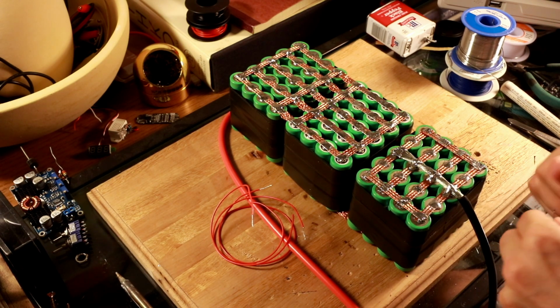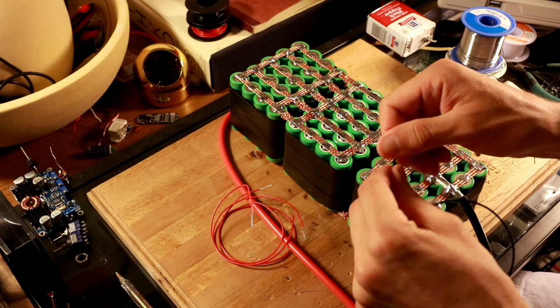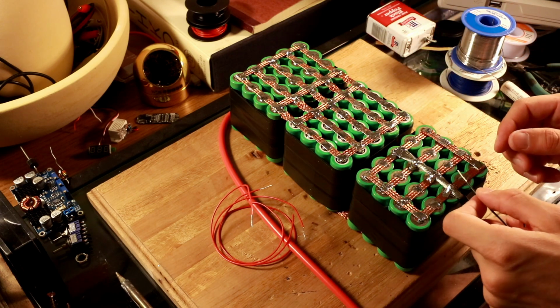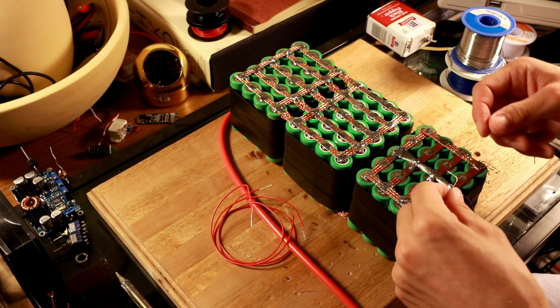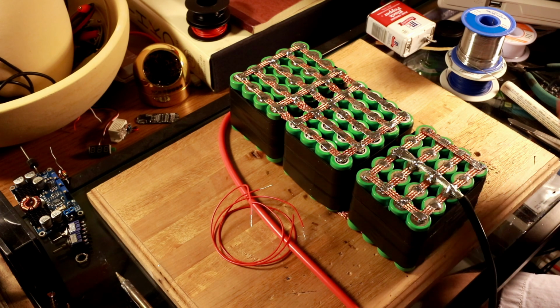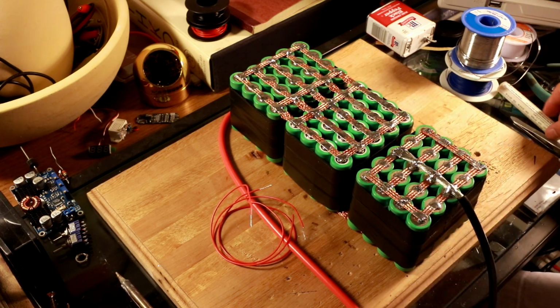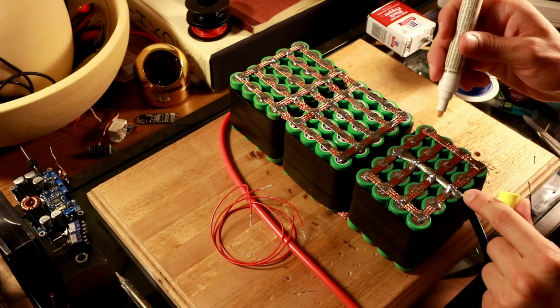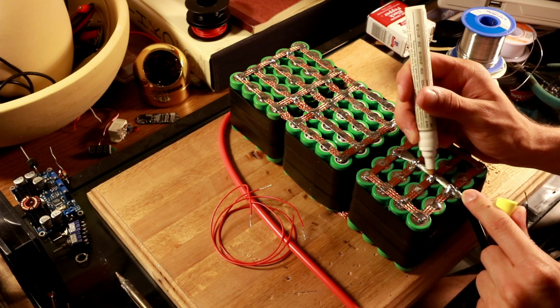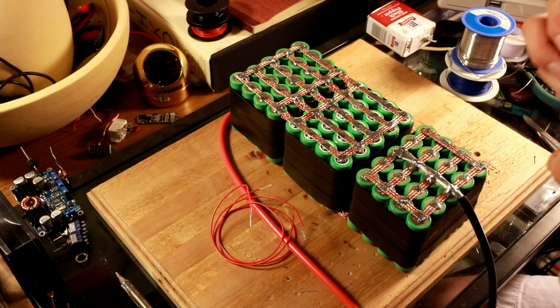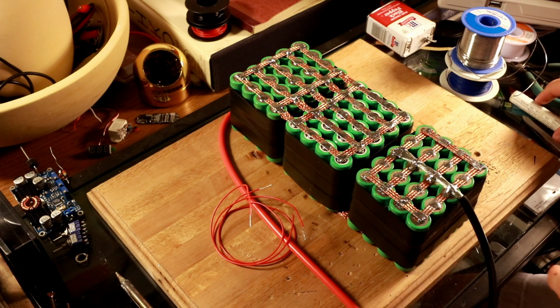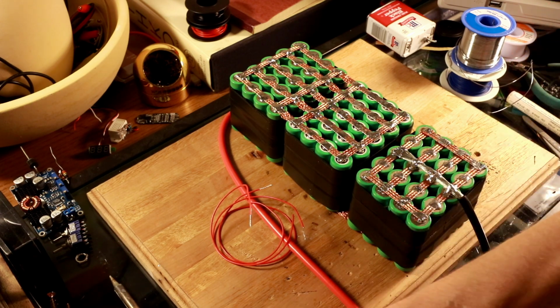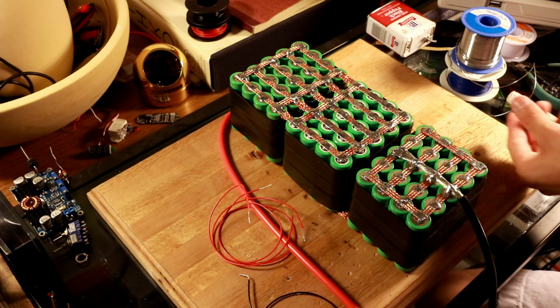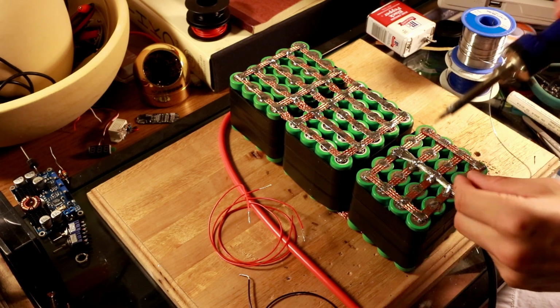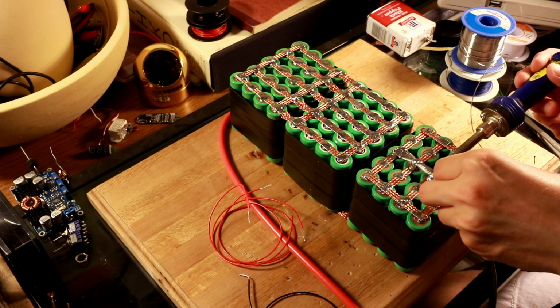For balancing, it's a little less critical where you place these because they're not going to be subjected to a lot of load. But in general, it's a good idea to keep them centralized so that you get the most accurate readout of the battery voltage possible. So I'm just going to tack mine onto this big negative cable in the middle so I get a decent reading of what voltage is on the majority of those cells.